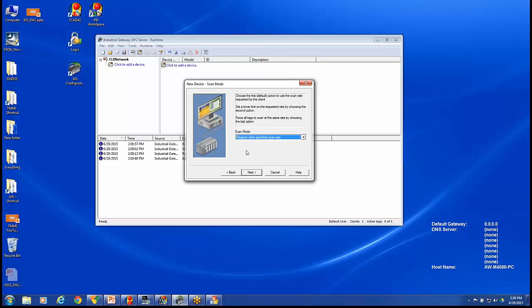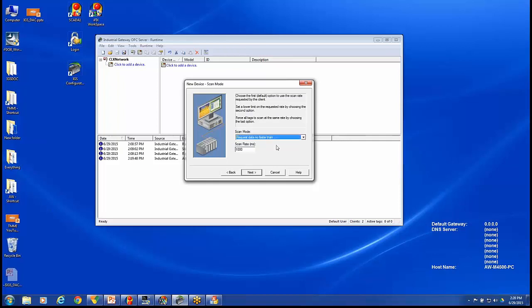Here we can set the scan mode for this device. If we respect the client specified scan rate, it will use the scan time for each tag in an iFix database to request the data. Or we have the option to come in here and set this to not request data any faster than 1,000 milliseconds. By doing this, we're controlling the rate at which this one device will work, and we can do this per device or per tag. I'll leave mine at 1,000 milliseconds for this device.